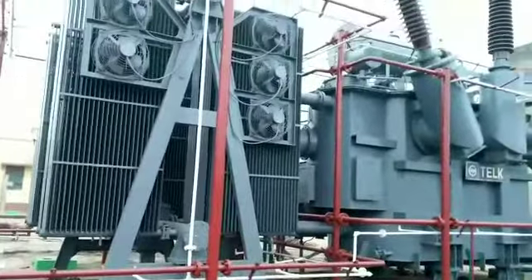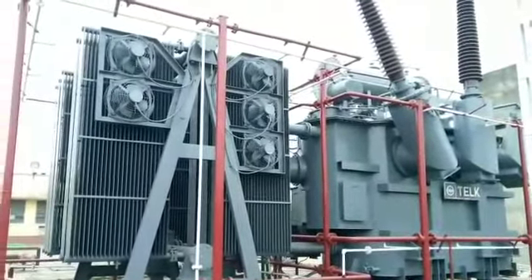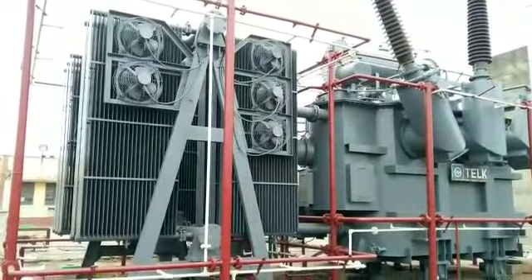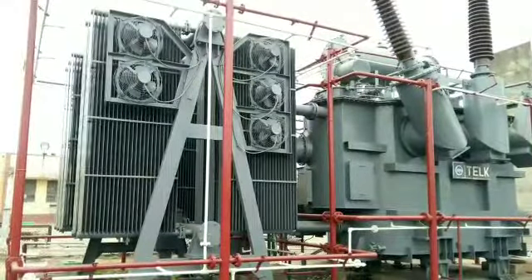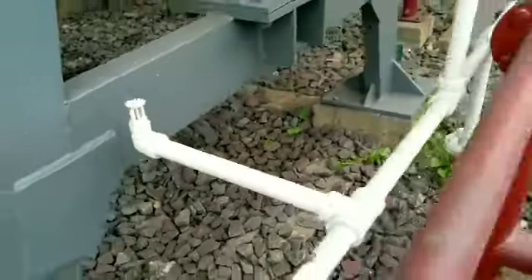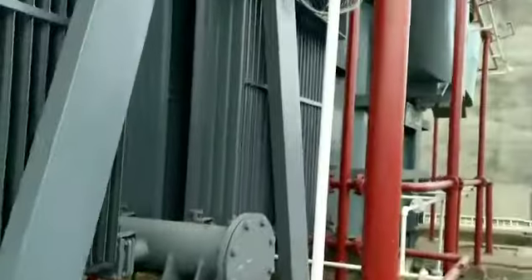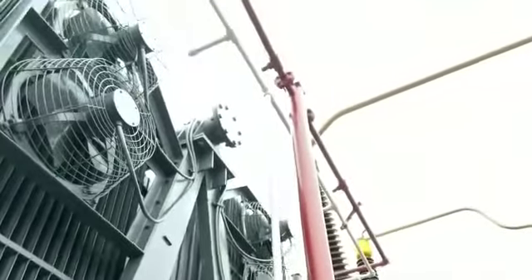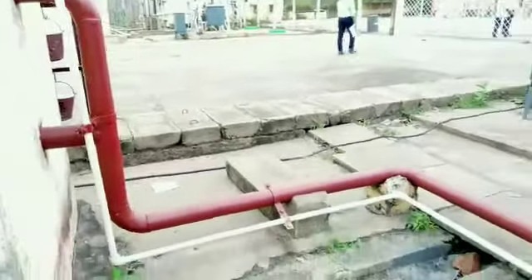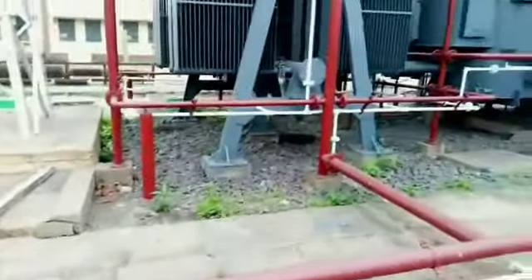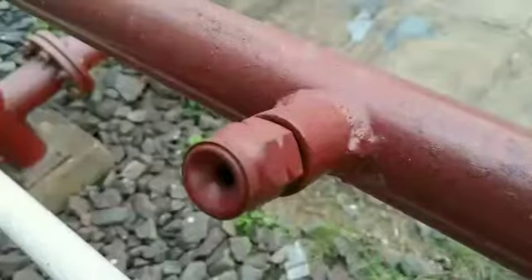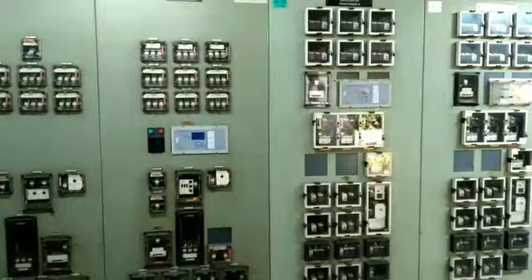Each substation has a unique system called Mulsifyre, which is used to safeguard the transformer from overheating or fire. If overheating or fire occurs, the glass tube placed near the transformer melts or bursts, the air pressure in the white pipeline is reduced, the diaphragm opens, and water is discharged on all sides of the transformer. All relays in the substation should be inspected periodically.